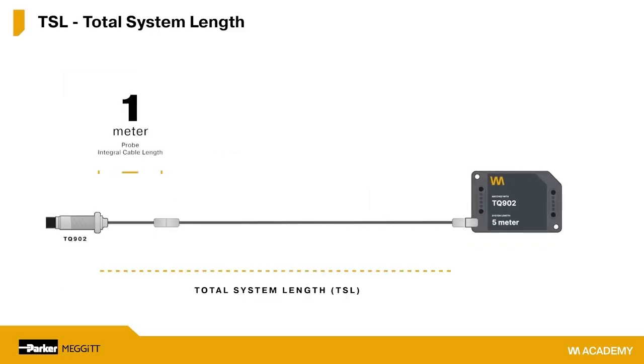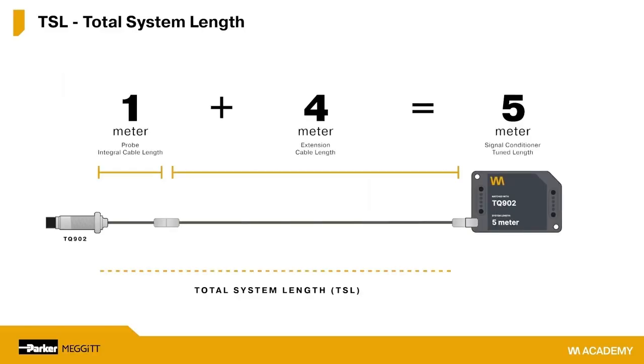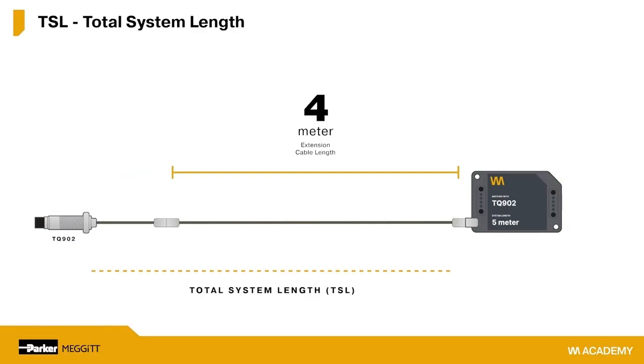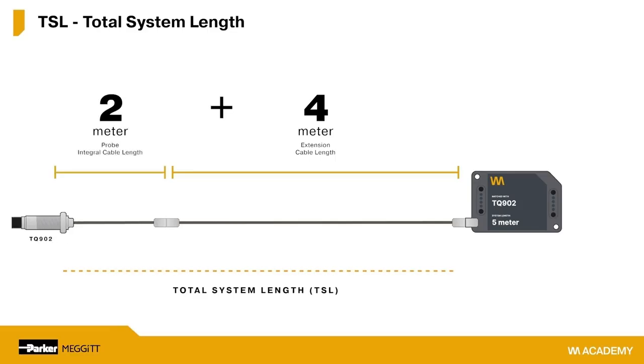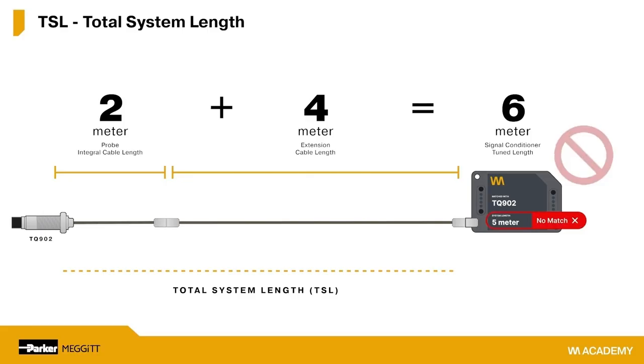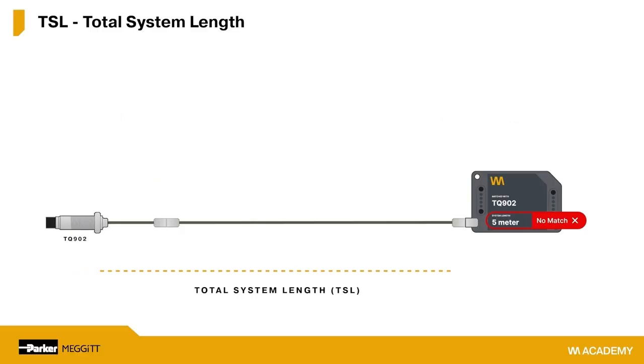To give you an example, if a probe has a 1 meter cable length and an extension cable has a 4 meter length, then a signal conditioner tuned for 5 meters should be selected. 1 plus 4 equals 5. However, if a probe with a 2 meter integral cable was used instead, the probe and cable would now become 6 meters in length and would not match the signal conditioner. 2 plus 4 equals 6, but the signal conditioner is for a 5 meter system.